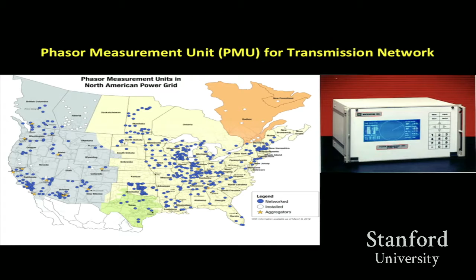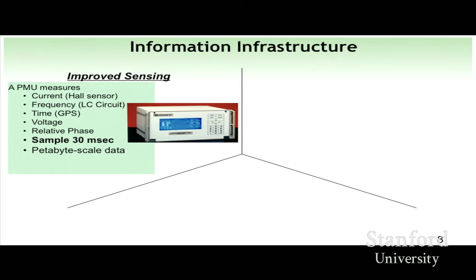This is what it looks like — it looks at data. These PMUs measure the current, the frequency (we're all at 60 hertz, but it's not exactly 60 hertz), the time with a timestamp, the voltage, the location, and the relative phase angle. It samples every 30 milliseconds and sends out data, and you're getting petascales of data now.